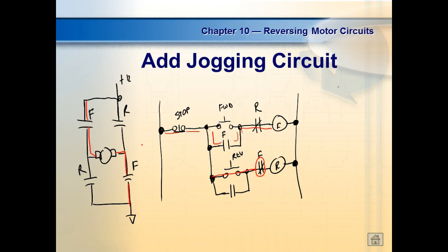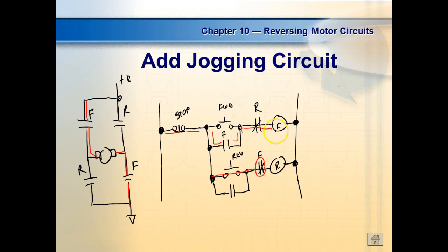And by the way, if you see this, it's just like on push buttons. We would have a dashed line running between this guy, and then it'll hit a V, and it'll come back and go to that one. If you see that, it's got mechanical interlocks. These dashed lines like this mean mechanically connected, right? We looked at that on push buttons. It's going to be in a V, better than what I've drawn.